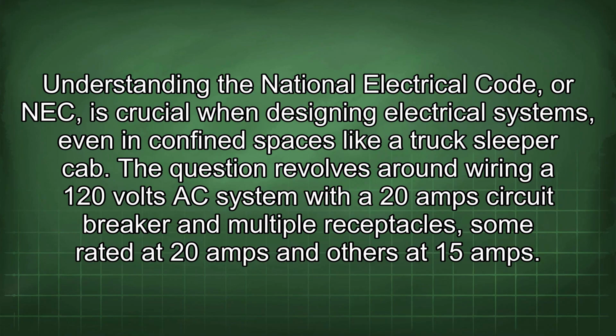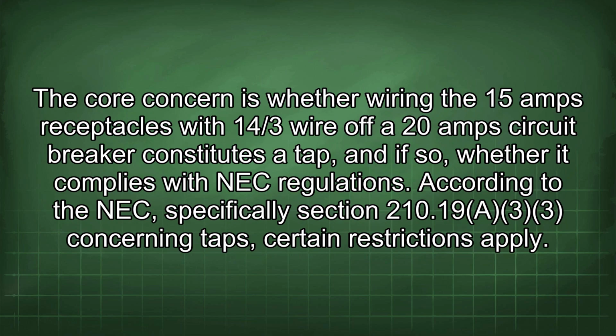Understanding the National Electrical Code, or NEC, is crucial when designing electrical systems, even in confined spaces like a truck sleeper cab. The question revolves around wiring a 120 volts AC system with a 20 amp circuit breaker and multiple receptacles, some rated at 20 amps and others at 15 amps. The core concern is whether wiring the 15 amps receptacles with 14/3 wire off a 20 amp circuit breaker constitutes a tap, and if so, whether it complies with NEC regulations.